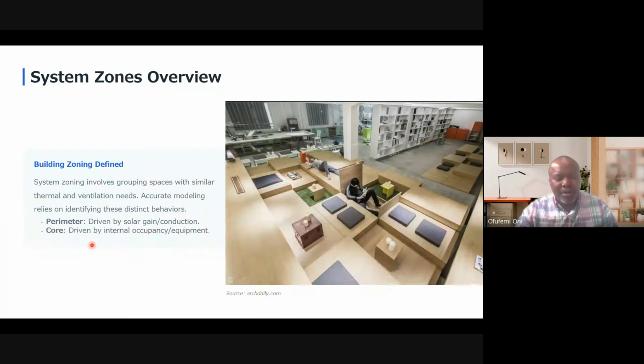If you look at the core of the building, that's where you have the office arrangement, people, equipment, and so on. So your HVAC load here is dependent on internal occupancy, equipment, and application—whether it's a gym or a production ground. This means the results on the perimeter will differ from those in the core, and this helps your system zone: you can use a different equipment to cool the perimeter and a different equipment to cool the core. So you can have multiple HVAC systems interwoven. I hope I'm making some sense on that.